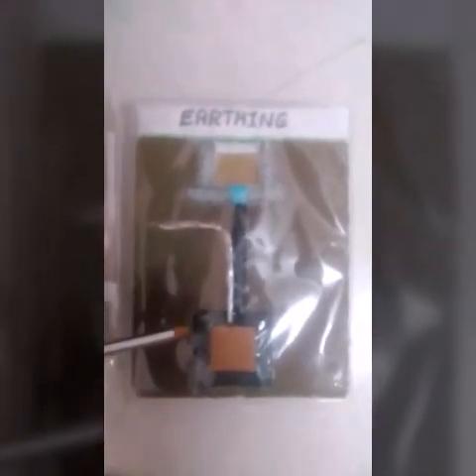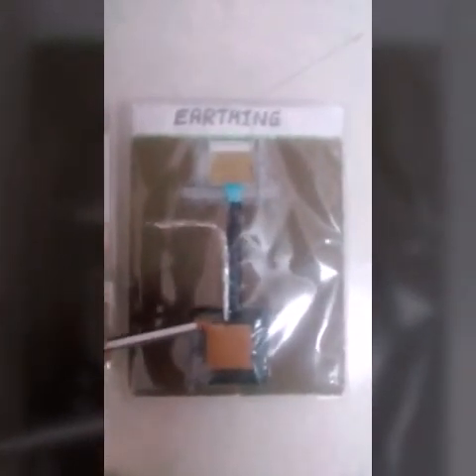This is the earthing plate we are talking about, and we can see the alternate layers of coke and salt provided here. The minimum thickness of this layer should be around 15 cm. We can see the earth wire taken out, which can be bolted with the help of a bolt. We can also see the funnel here, which is provided to supply moisture to the plate.